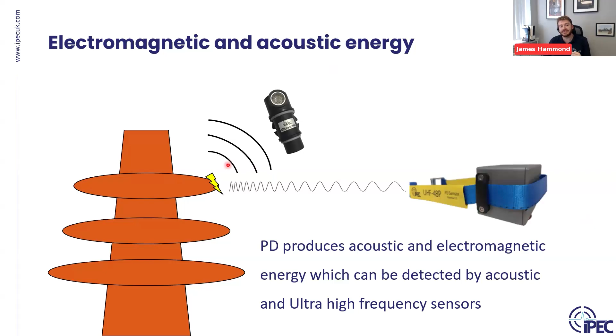And then if you have a different type of sensor, an ultra high frequency sensor, that same pulse of energy in the ultra high frequency range can be detected that way as well. So just going through a couple of the installations of what it would look like physically. You can see here your HFCT around the earth sheaths of the cable.